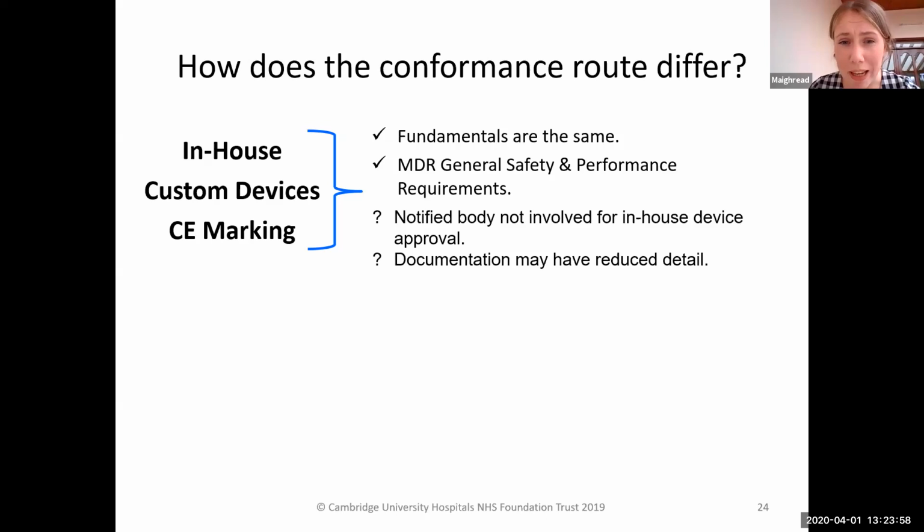Regarding the difference between an in-house and a CE marking, you may not have to involve a notified body for an in-house device, whereas if you want to CE mark it, you then have to have your technical file reviewed by a notified body. But in terms of that body of work, it would still be the same.